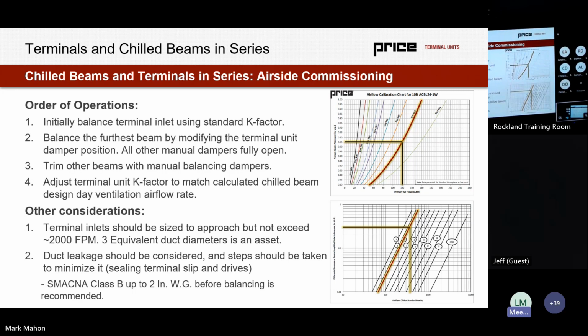Other considerations that are really critical is the terminal inlet should be sized to approach but not exceed that 2,000 feet per minute. And we should try to have 3 equivalent duct diameters. That would be an asset upstream of the terminal, especially in a chilled beam system. I think it's even more critical. And we also need to consider duct leakage, and steps should be taken to minimize it, such as sealing terminal slip and drives if we have a reheat valve or a silencer or a reheat coil, pardon me.